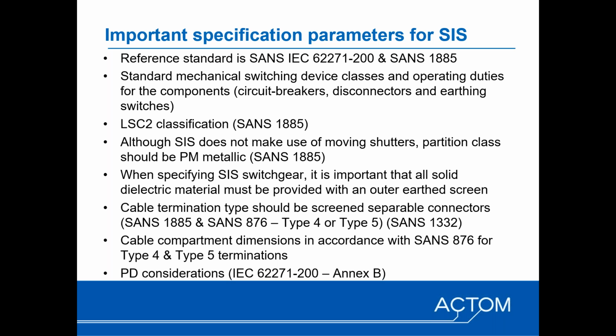It's also important to bear in mind, in terms of continuity of philosophy, that the cable terminations should also be screen separable, or should be done using screen separable connectors. Those are well defined in the SANS standards. So the accessories are covered by SANS 1332, which was previously NRS 053. That's been adopted as a standard, so the requirements for the cable terminations are covered in SANS 1332. But it is also specified through SANS 1885 and SANS 876.